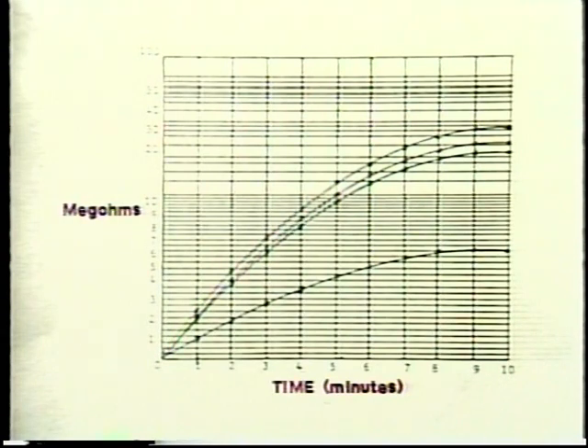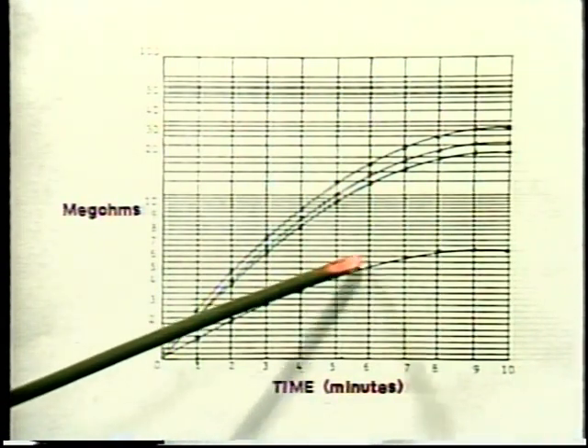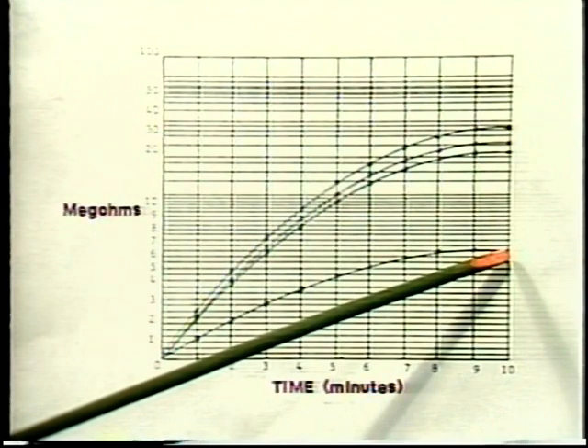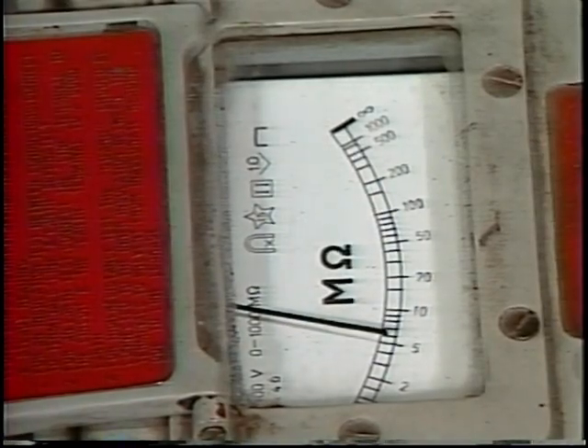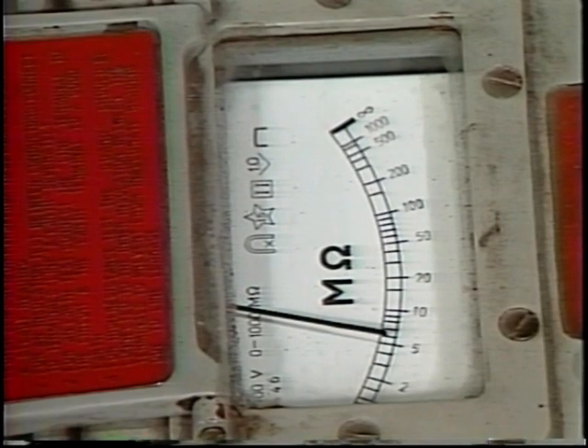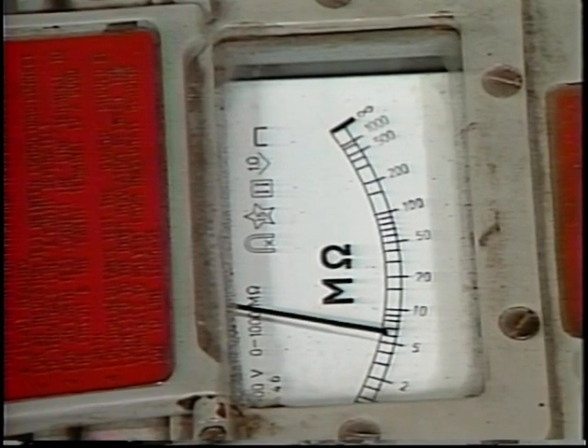If the reading levels off quickly at a fairly low level, however, it is a sign that leakage current is flowing through or over the insulation. This current will probably cause further insulation breakdown until shorts develop and the motor fails.